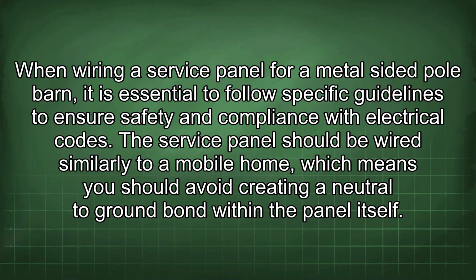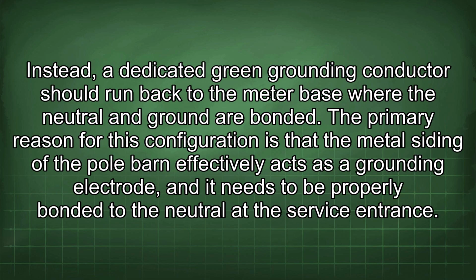When wiring a service panel for a metal-sided pole barn, it is essential to follow specific guidelines to ensure safety and compliance with electrical codes. The service panel should be wired similarly to a mobile home, which means you should avoid creating a neutral to ground bond within the panel itself. Instead, a dedicated green grounding conductor should run back to the meter base where the neutral and ground are bonded.